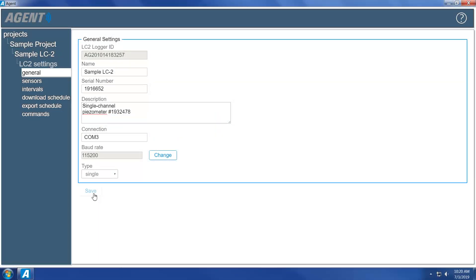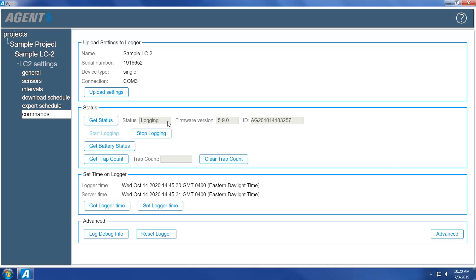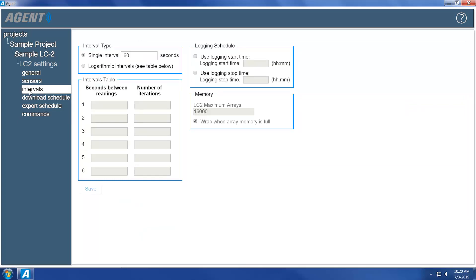The LC2 will not collect data from internal or external sensors until logging has been initiated by the Agent program. To start logging data, click Commands. Next, click Set Logger Time to overwrite the date and time stored on the logger with the local time and date. Click Start Logging to have the LC2 begin logging data. The status field will now display 'logging' to show that the LC2 is logging data. The interval at which readings occur can be changed using the Intervals screen. By default, the LC2 will take a reading every 60 seconds. For information on setting the logging intervals, please refer to the Agent Instruction Manual.